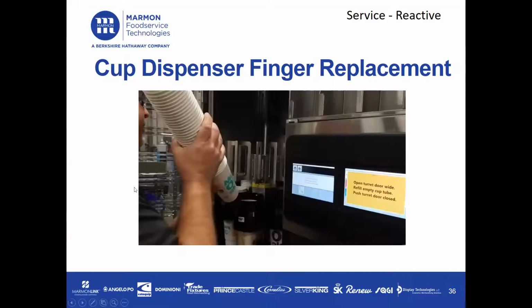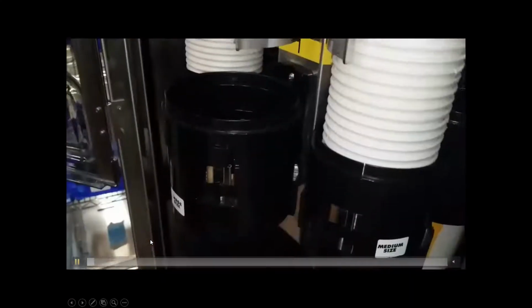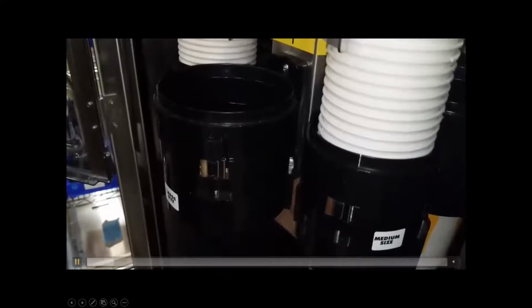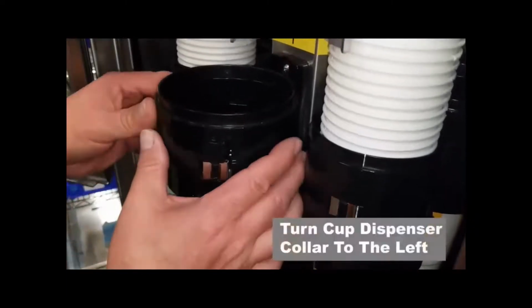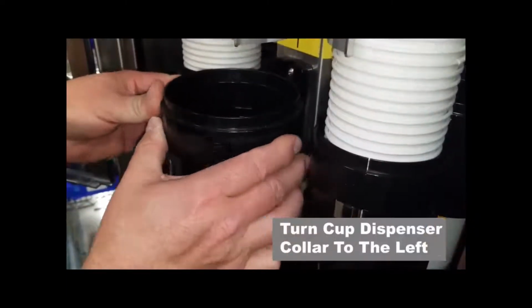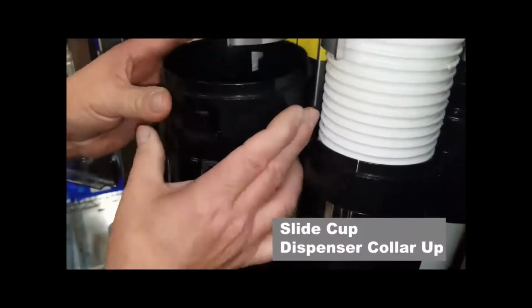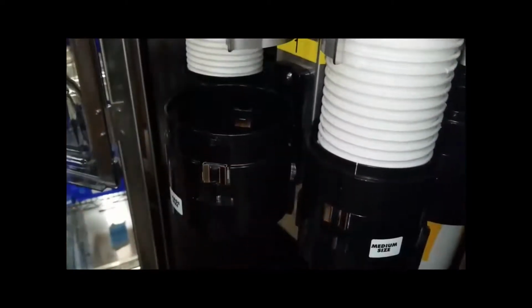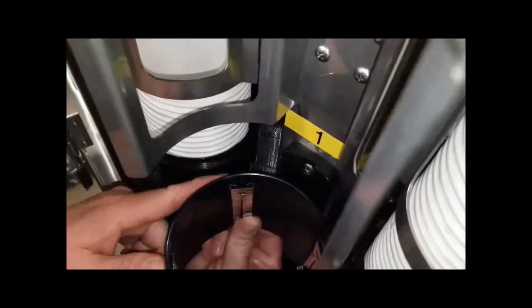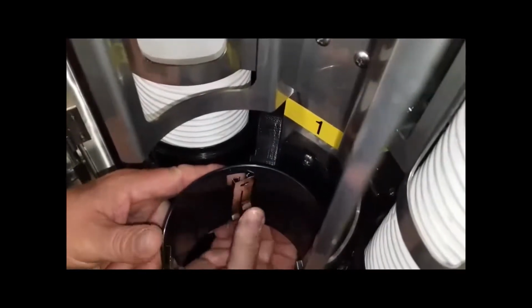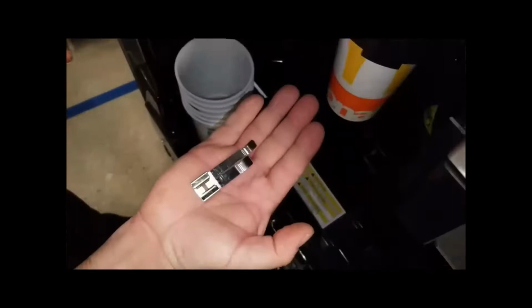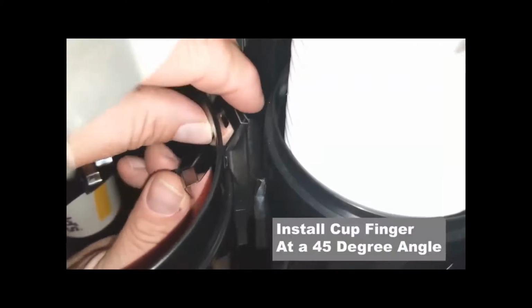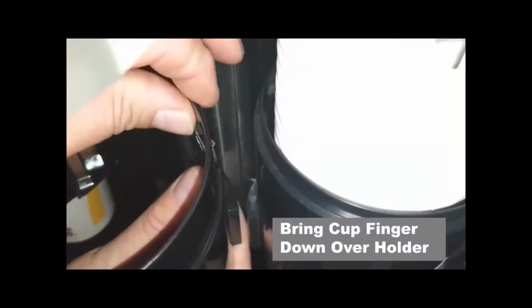Finger replacement. To replace the fingers out in the field, you want to remove the lock ring off the cup dispenser. Once you have this lock ring off, it exposes the fingers. And at this moment, as I told you guys before, you don't need any tools. You just push the fingers off the cup dispenser. And to add the fingers back and replace them with new ones, just put it in at an angle, a 45-degree angle, and just slide it back into the cup dispenser.